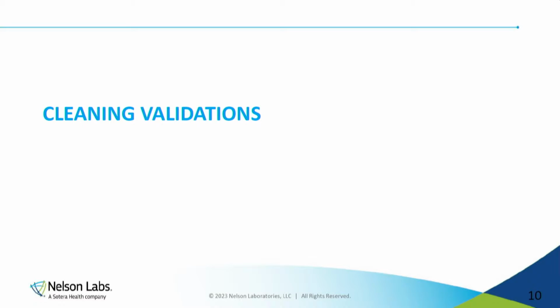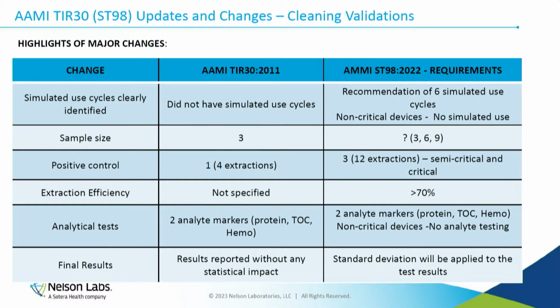Now I'm going to go through what changes have occurred in the cleaning validation realm. If you're not aware, TIR30, which was used for cleaning validations, has been updated to AAMI ST98. This is the first standard in the world that talks about reprocessing validations for cleaning. Okay, there's no other one. So if you are submitting all over the world, they are using this document as a backbone. Notified bodies in Europe are using this as well, just to make sure that you are compliant to the standards that do specify that.